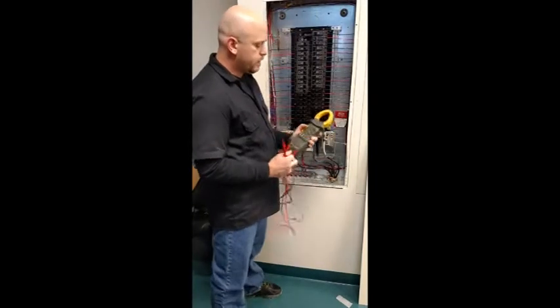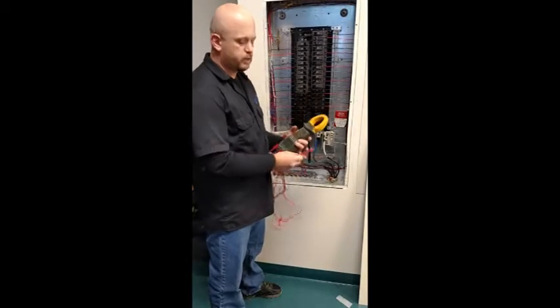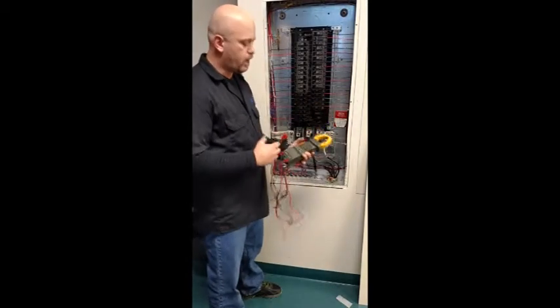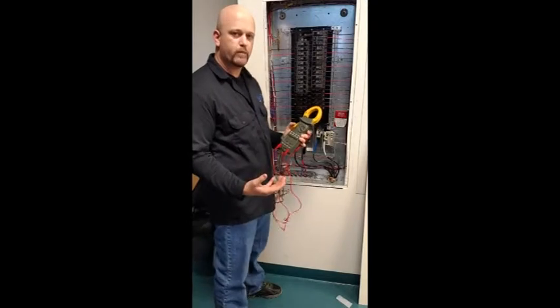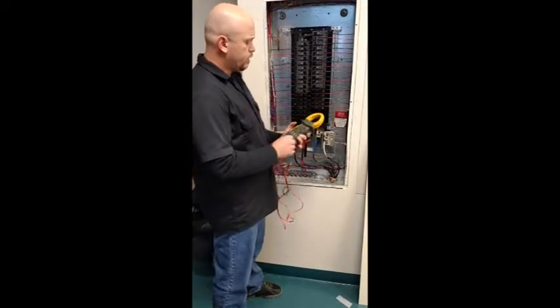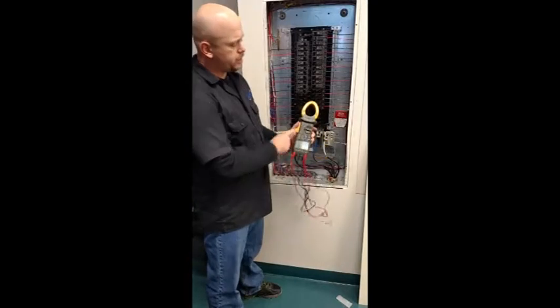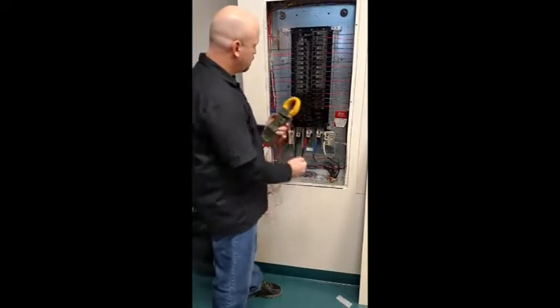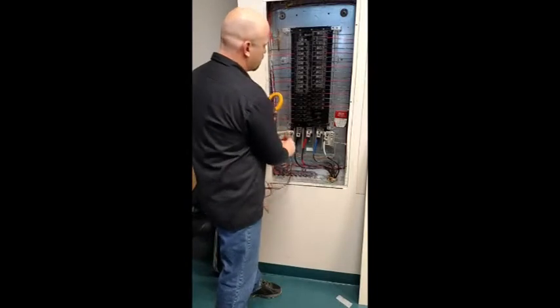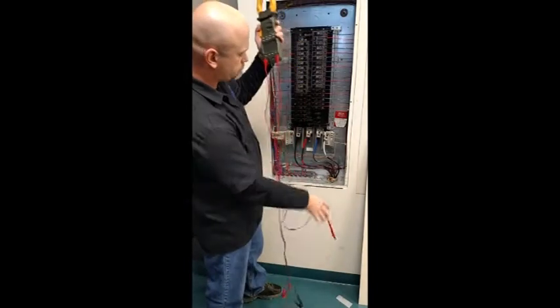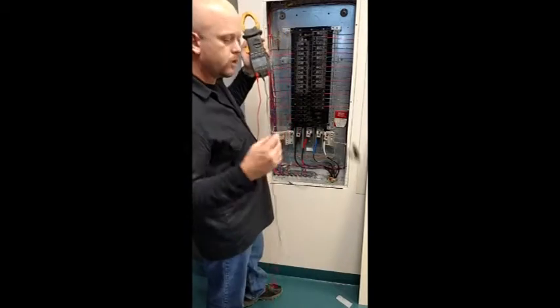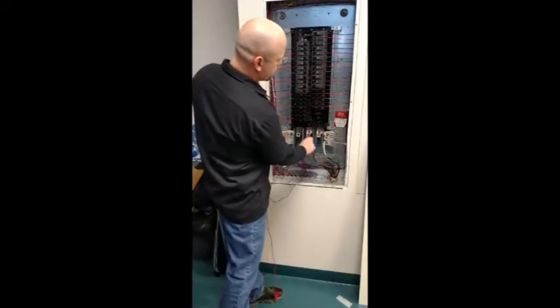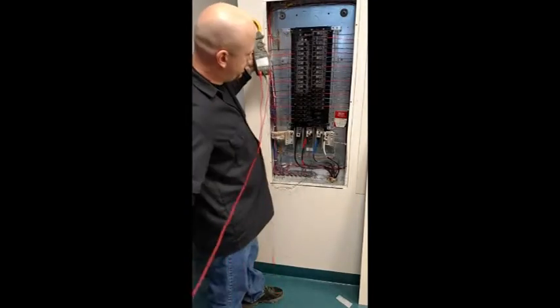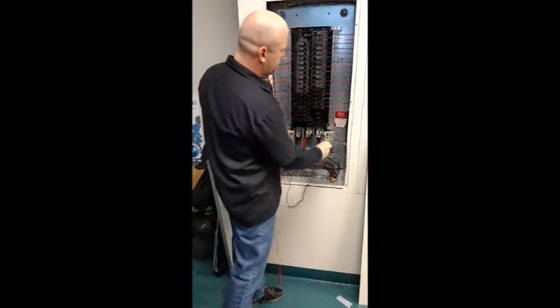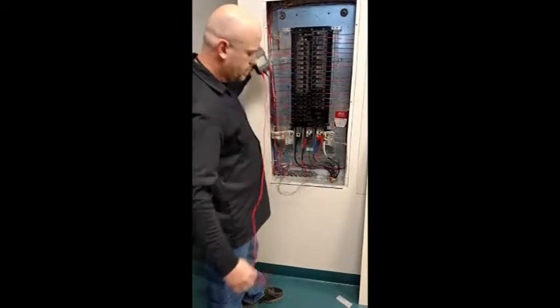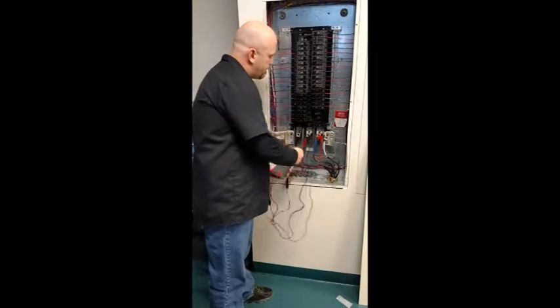When you're doing a three-phase delta, and often when you're doing a three-phase panel, it's beneficial to check both the delta and the Y circuitry. There's actually 6 circuit pathways in a three-phase environment. You will need to turn your meter to the three-phase selection, which is 3 clicks to the left. And you will then take your two clamps off the neutral, and we'll want to take the V2 common clamp and lock it onto the lug for the B phase, and the V3 clamp and lock it onto the C phase lug, and we will probe and clamp the A leg.